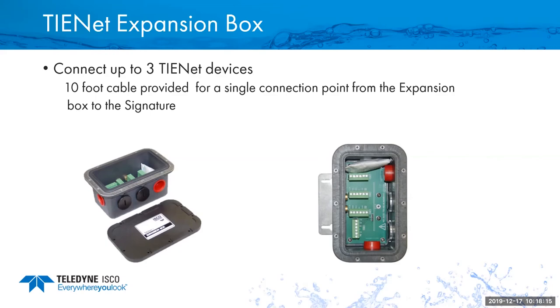The TIENet bus that we use to communicate to our sensors allows us to use just that one cable to go all the way back to the signature, therefore reducing the amount of wires that you have to run the entire distance back to the signature. Also, the TIENet expansion box gives you the ability to add another analog input card or output card or contact closure in addition to the three different TIENet devices that you can run into this.